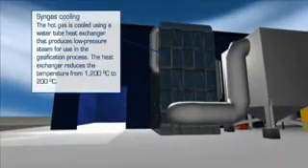Now let's take a look outside. The hot syngas exits from the plasma converter at approximately 1200 degrees Celsius and is then cooled in a water tube heat exchanger to reduce the gas temperature to 200 degrees Celsius.